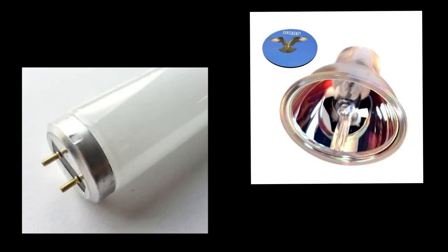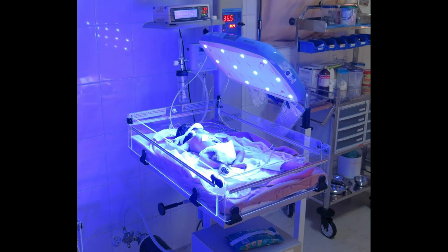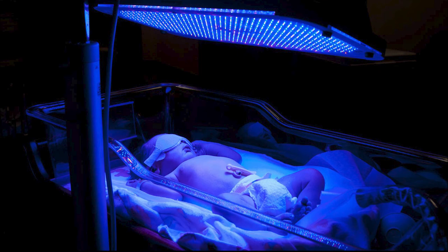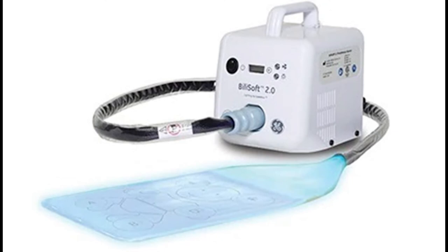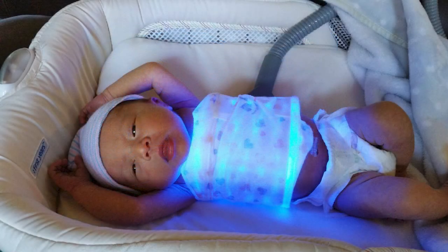There are several types of lights used to treat jaundice. Radiant lights can have fluorescent or halogen bulbs. There are also bili-lights, which rely on specifically engineered LEDs that produce a pure blue light and eliminate most of the harmful UV light that normal bulbs can produce. The LEDs can be arranged in a grid pattern or used with fiber optics. One of the most versatile applications is the LED fiber optic blanket, which can be wrapped around the baby so they receive treatment from all angles.